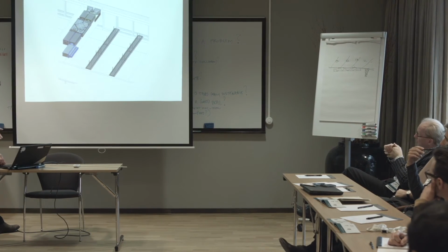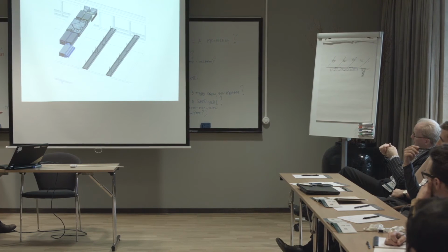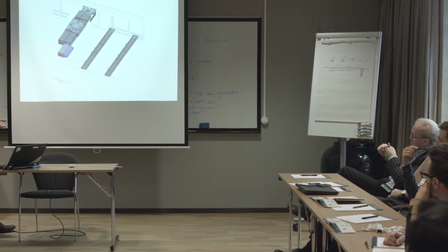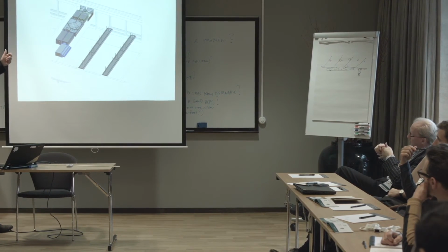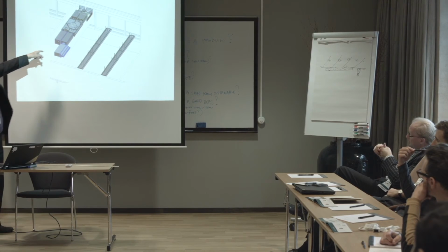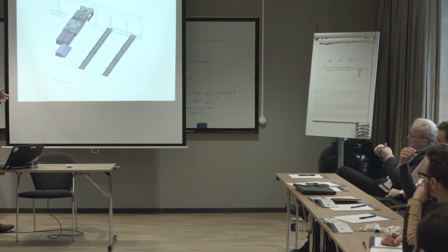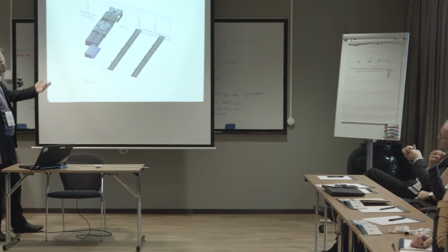We've got 3 kilowatts of heat from the children. It's only 30 days a year when you actually need any heat. And the extra that you've got to put into the fan to make this work through the filters, it's got 2 fans instead of 1. So this actually works out more energy inefficient than the previous system.